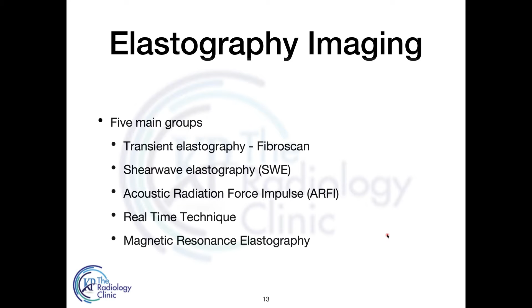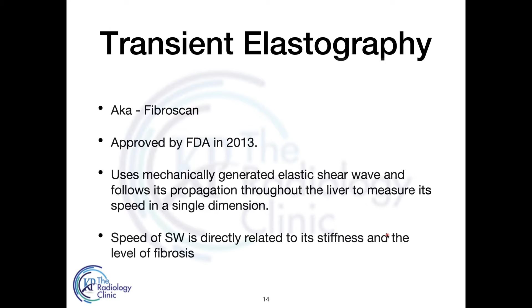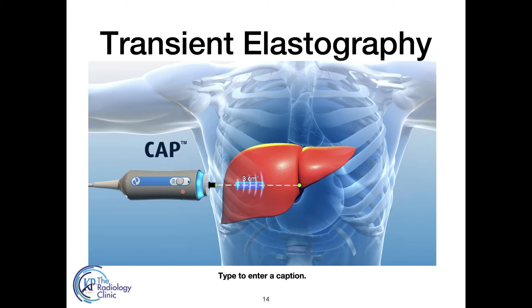and magnetic resonance elastography. Transient elastography, also known as FibroScan, was approved by the FDA in 2013. It uses a mechanically generated elastic shear wave and follows its propagation throughout the liver to measure its speed in a single dimension. The speed of the shear wave is directly related to the stiffness and the level of fibrosis. So this is how transient elastography is done. The probe here gives a mechanical impulse, and the speed of that impulse traveling through the liver is calculated.